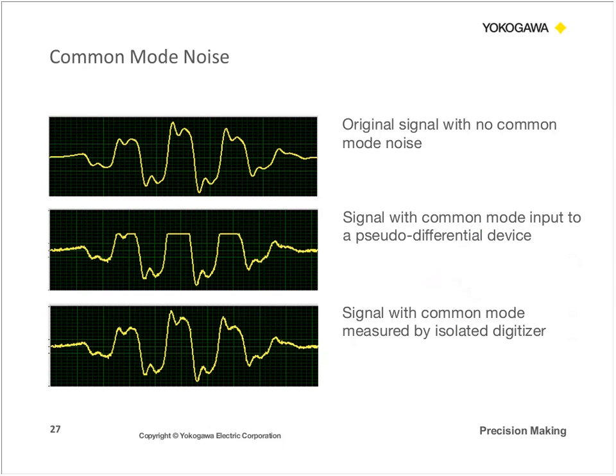So if you're using a pseudo-differential device to measure the battery cell or the fuel cell and you have common mode noise, what's going to end up happening is the signal's not going to be recreated accurately because there's going to be influence of common mode voltage. But if you measure the signal using an isolated digitizer, you're going to see that it's going to accurately recreate the original signal with no common mode noise.